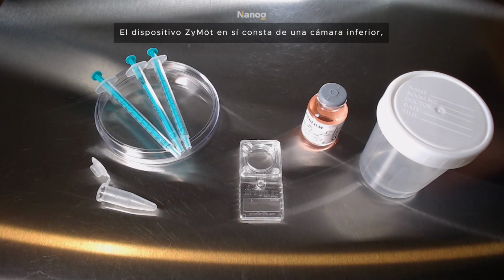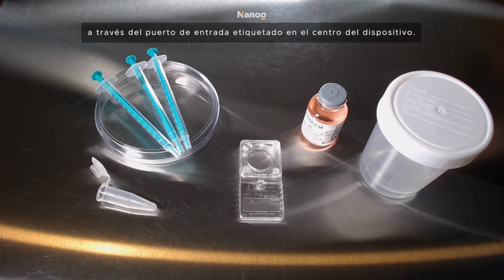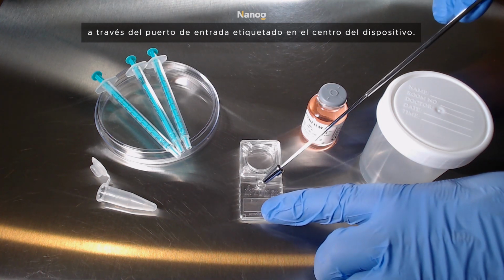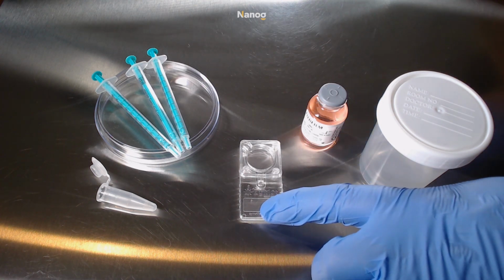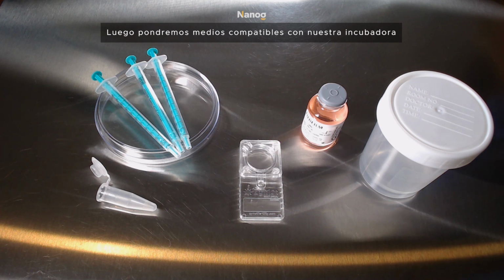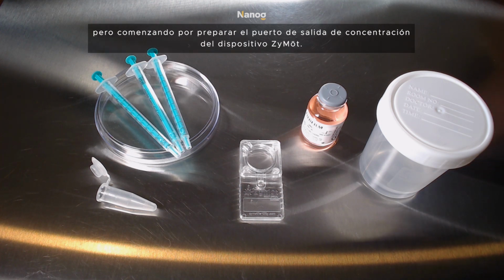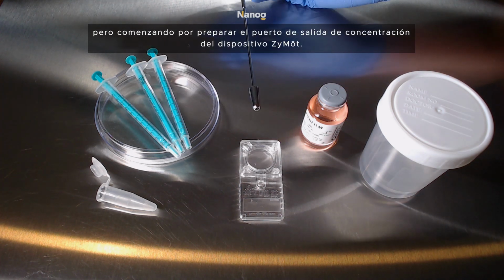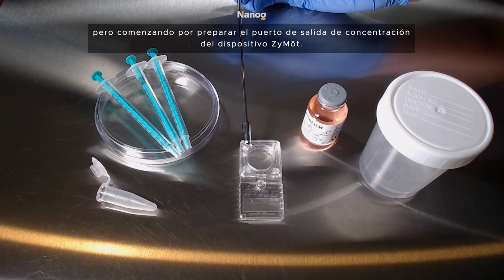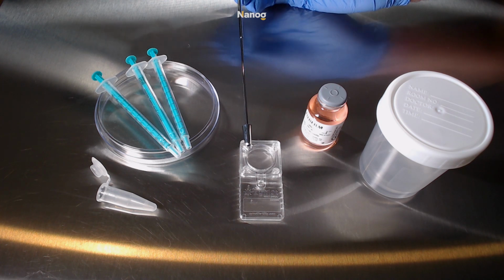The ZyMot device itself consists of a lower chamber in which we will load our raw, unwashed semen via the labeled inlet port in the center of the device. We will then overlay media compatible with the incubator that we plan to use onto the upper chamber of the device, but starting by priming the concentration outlet port of the ZyMot device.